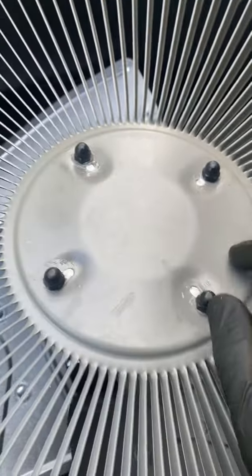See if I can tug on it. Motor seized up — rain gets on these open spots, goes on top of the motor, seizes the rotor to the stator, causes a bunch of rust in there. So this is how I prevent the issue from reoccurring.